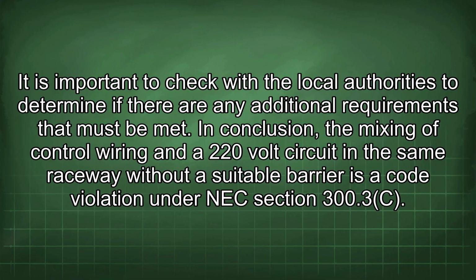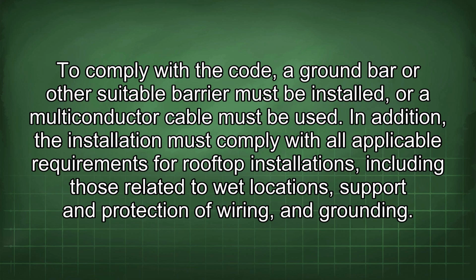In conclusion, the mixing of control wiring and a 220-volt circuit in the same raceway without a suitable barrier is a code violation under NEC Section 300.3c. To comply with the code, a ground bar or other suitable barrier must be installed, or a multi-conductor cable must be used. In addition, the installation must comply with all applicable requirements for rooftop installations, including those related to wet locations, support and protection of wiring, and grounding.